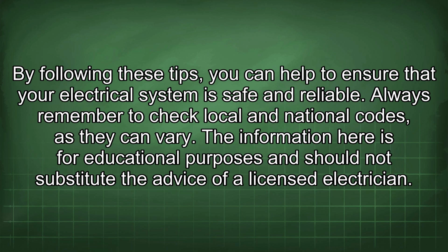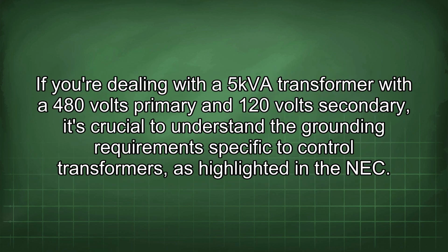Always remember to check local and national codes as they can vary. The information here is for educational purposes and should not substitute the advice of a licensed electrician. If you're dealing with a 5kVA transformer with a 480 volts primary and 120 volts secondary, it's crucial to understand the grounding requirements specific to control transformers, as highlighted in the NEC.